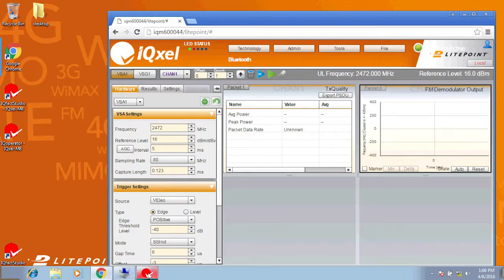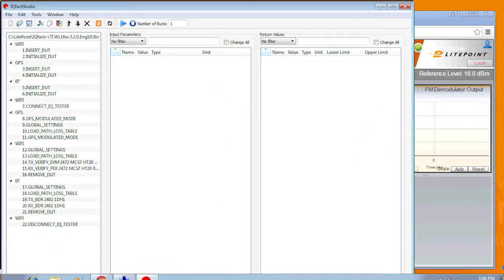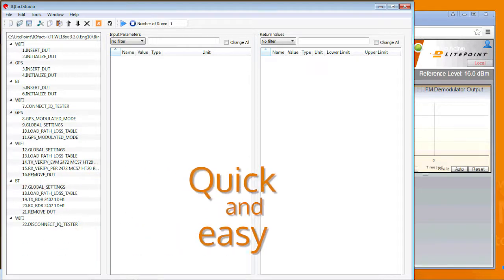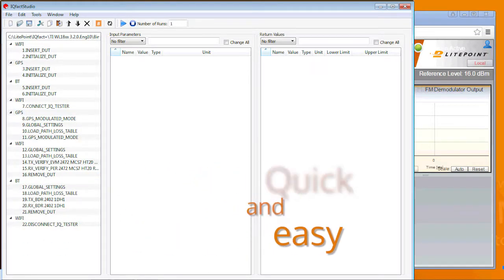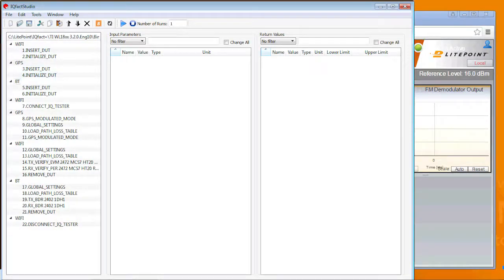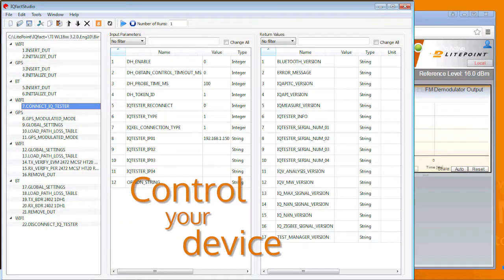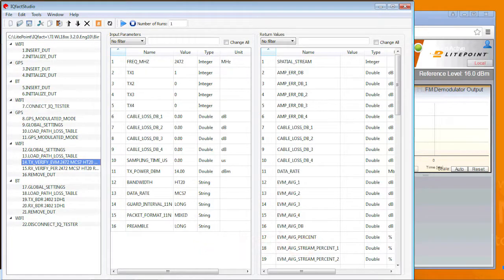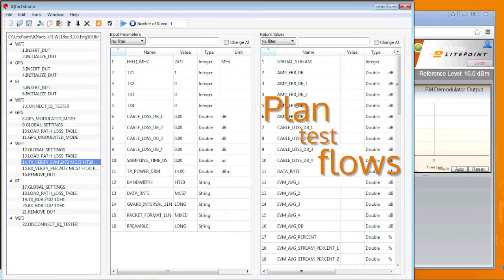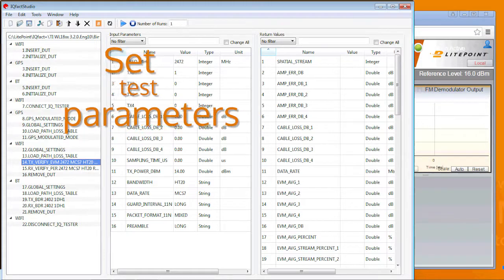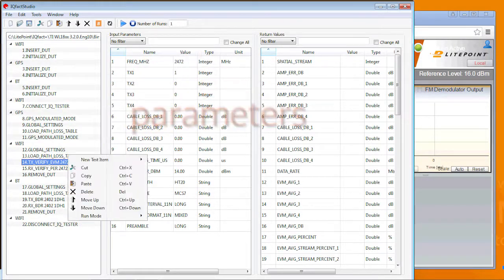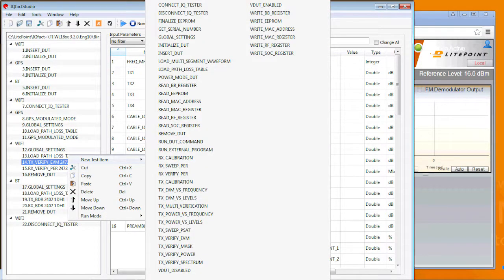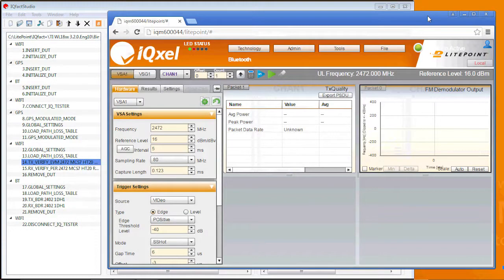Now I'm going to use LitePoint's IQFACT Plus software and show you how quick and easy it is to design and run a test with iQxel. IQFACT Plus lets you control your device and the tester, plan test flows, and set test parameters. Adding a new test is very easy. Simply right-click where you want to insert a test and add a new test item.